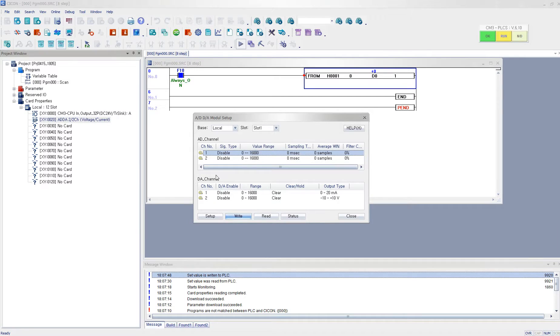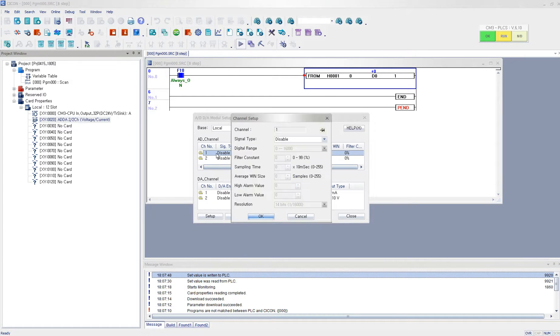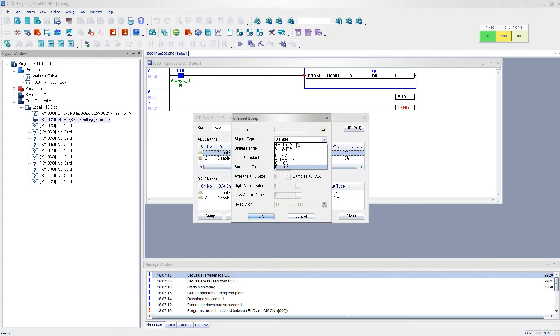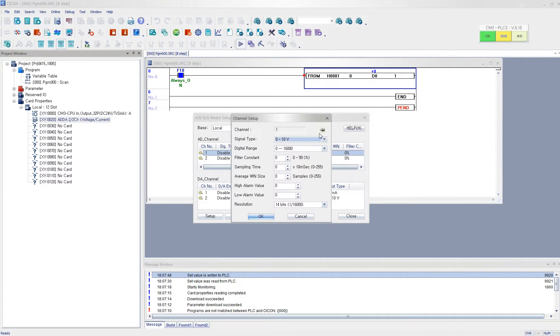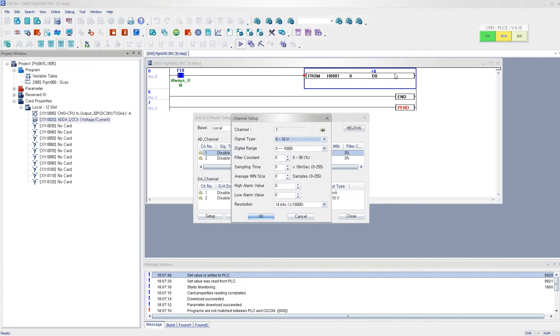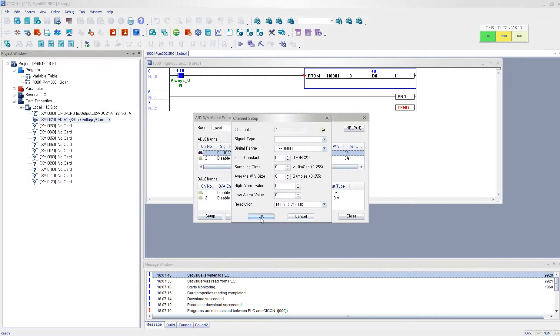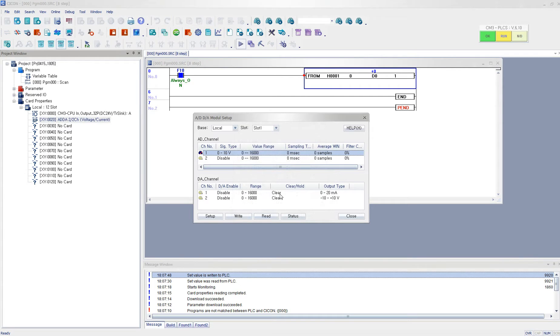But now I'm going to use one channel, channel 1. And I'm going to read from 0 to 10 voltage and convert it to the digital range from 0 to 16,000. So this means that if I'm getting a 5 voltage, then it should be 8,000 on the digital range, digital value. And I click OK.